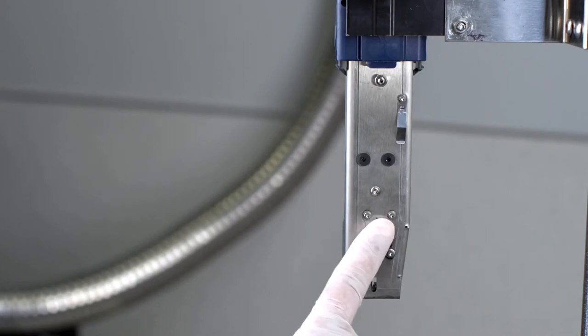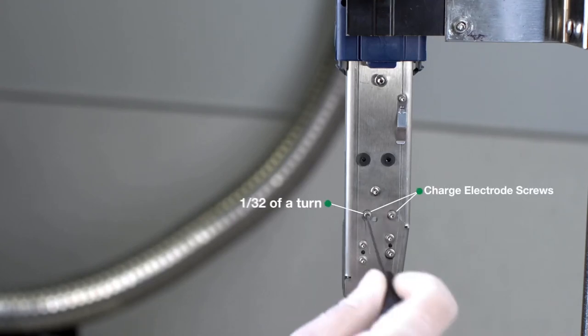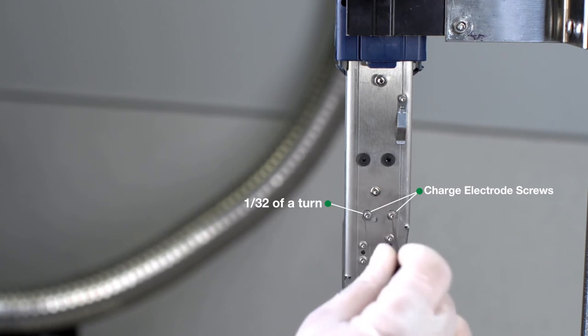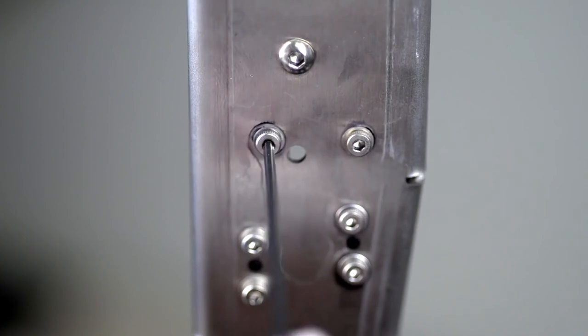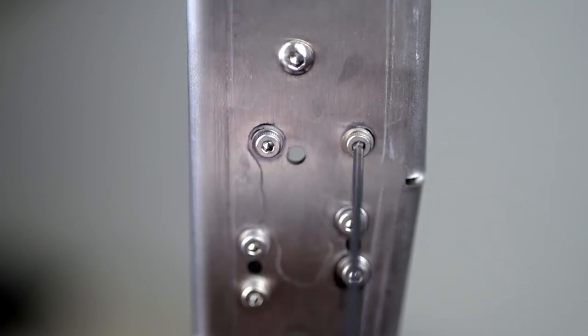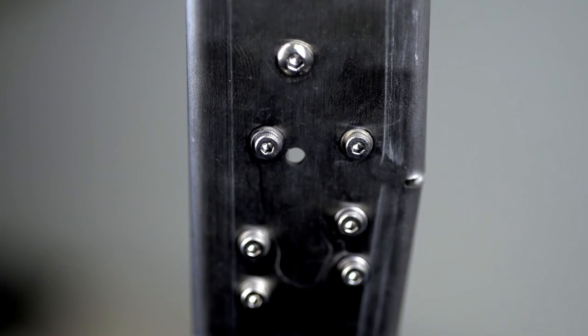Next, loosen the two charge electrode screws located on the back of the unit by turning them 1/32nd of a turn. These screws need to be loose enough to allow for adjustment, yet tight enough to hold the charge electrode in place.